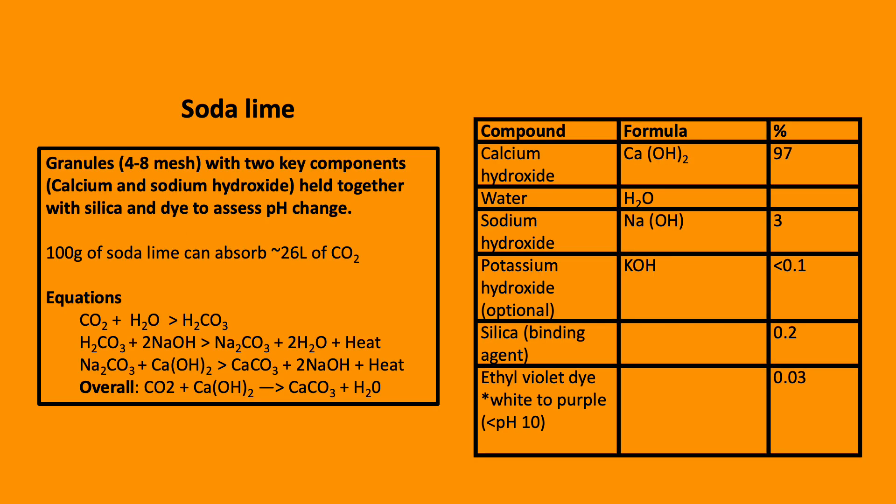Soda lime is a white-grayish coloured crystalline solid and has two key features. It reacts with carbon dioxide, thus removes CO2 from the circuit, and also provides an element of humidification of the system. It is presented as granules of 4-8 mesh. The granules will pass through a mesh which is 4 holes per square inch, but not 8.